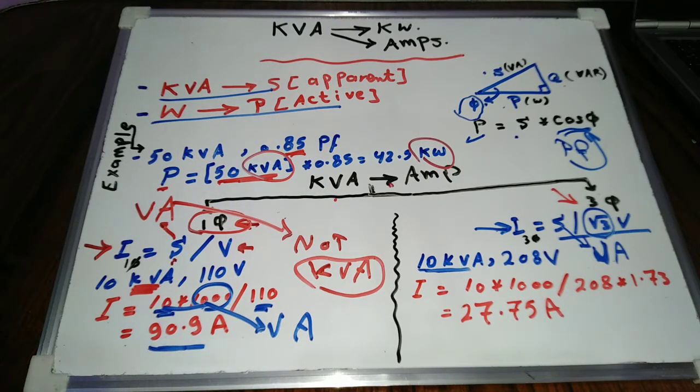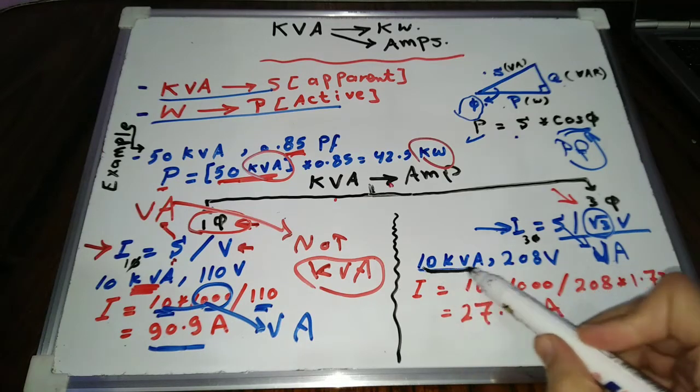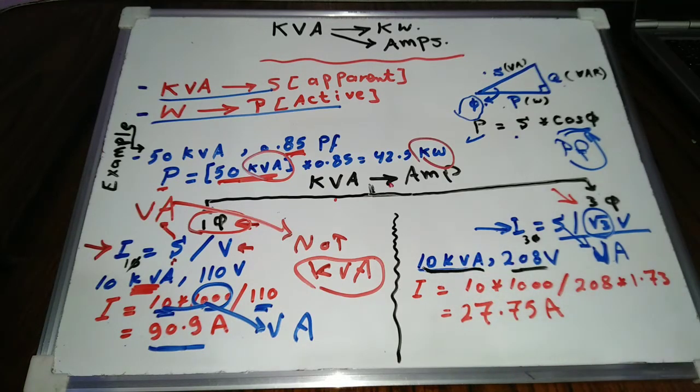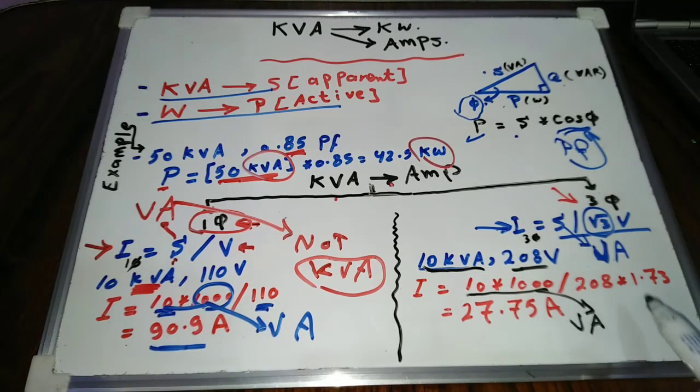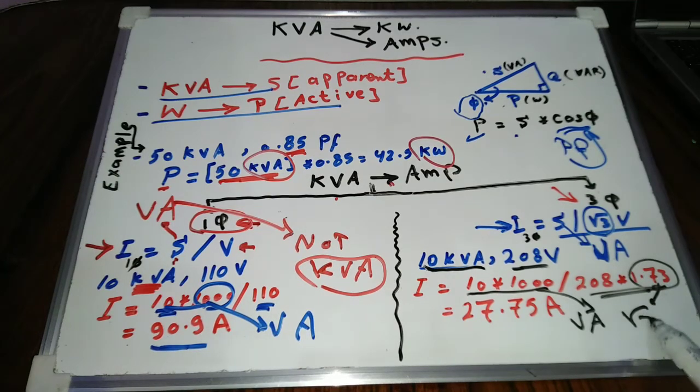If we have a three phase load of 10 kVA and operating voltage of 208 volt, then the current of this load equals 10,000 divided by 208 times 1.73, equals 27.75 amps.